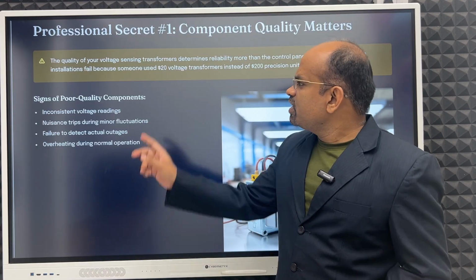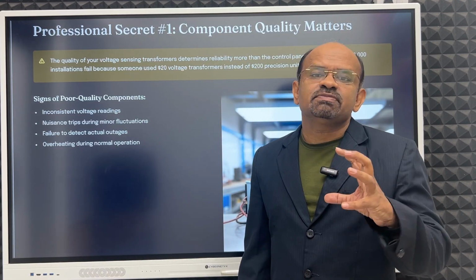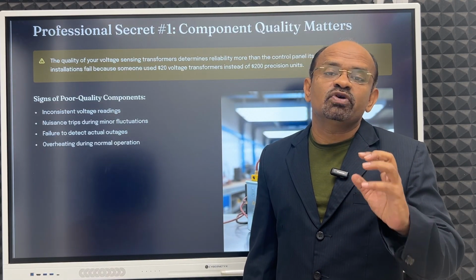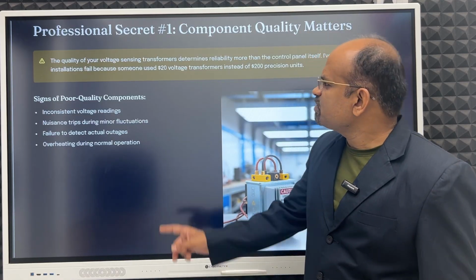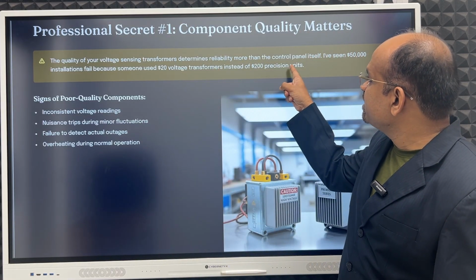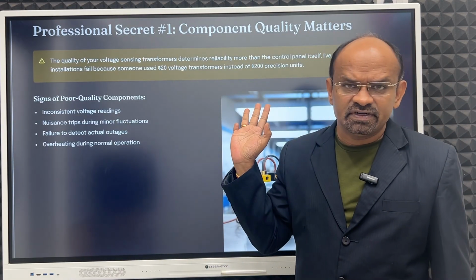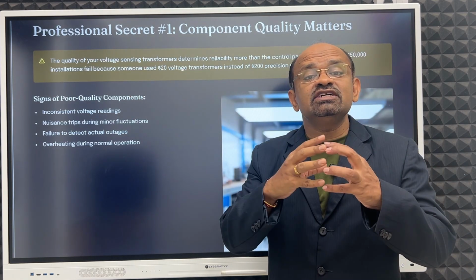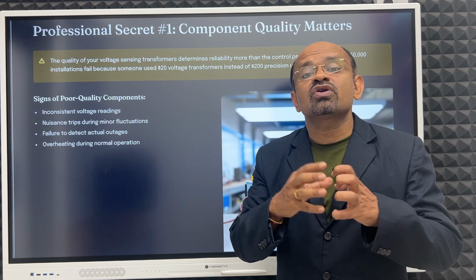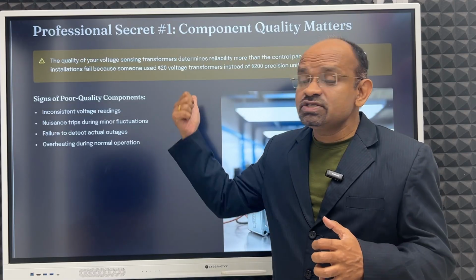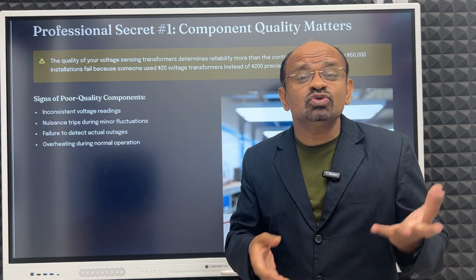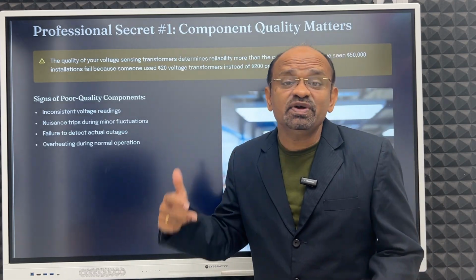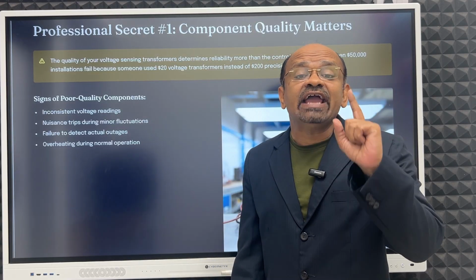See, your voltage sensing transformer, PT we call it, potential transformer or voltage sensing transformer, determines the reliability more than the control panel itself. Because if it does not determine whether there is a proper voltage at the input, the panel will not be able to take the decision whether to start the DG or not. That is why it is very important. It should sense accurately.